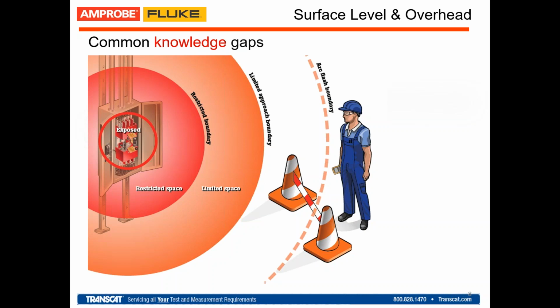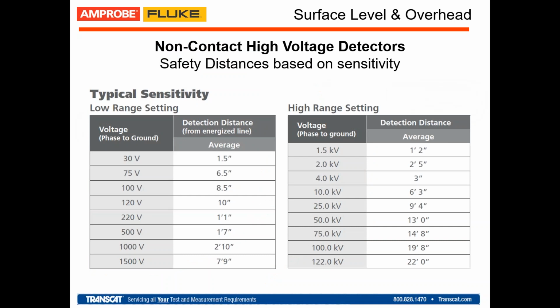So, long story short, where do high voltage NCVs, or non-contact voltage detectors, play a role here? Depending on the voltage of the line, all NCV detectors provide sensitivity tables that can be associated with the safety distances, right? So if you buy, let's say, an Amprobe TIC 300 NCV that has a detection range of 30 volts to 122 kV AC, you will have a sensitivity table in the user's manual. And if you plan to work on an overhead substation dealing with 34.5 or 19.9 kV and you're using one of these devices, you might know that the equipment will detect voltage at a minimum distance of between 9.4 and less than 13 feet, right?